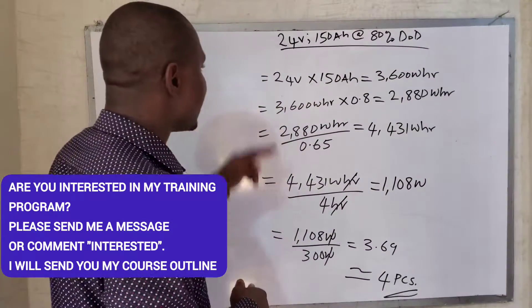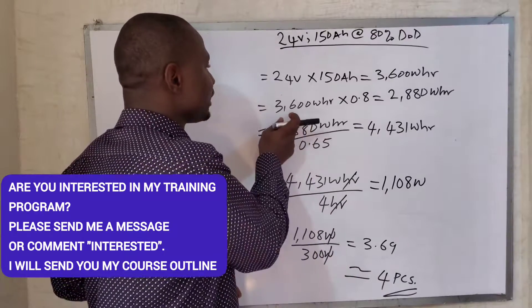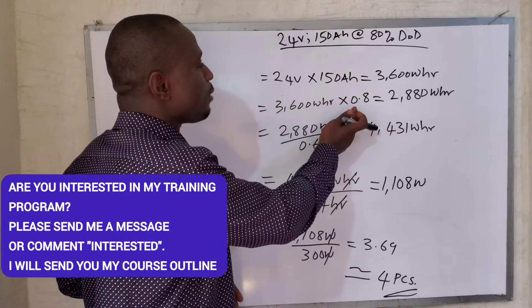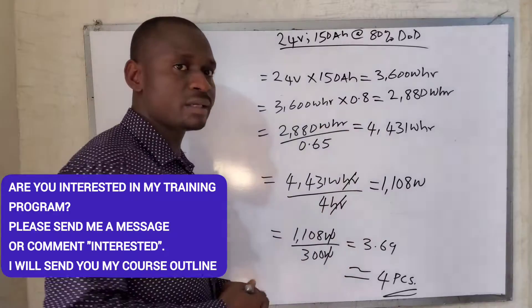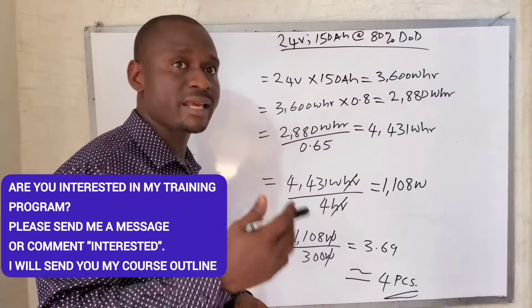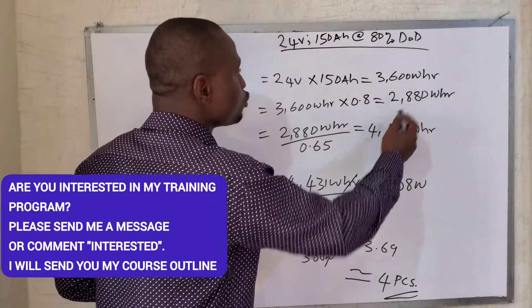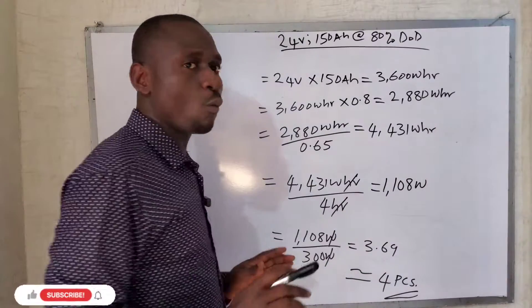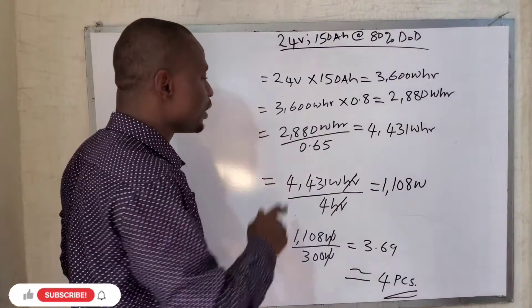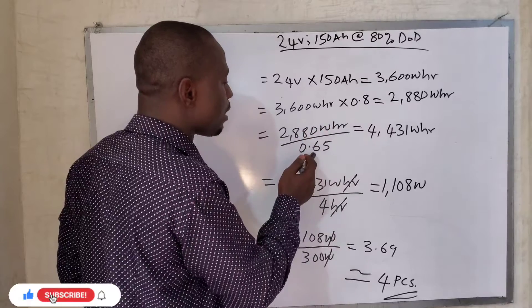Now at 80% DoD, it will be 3,600 watt-hours multiplied by 0.8 (that's 80 divided by 100). This will give you 2,880 watt-hours. Now in the next step, you divide this 2,880 watt-hours by the performance ratio of the solar panels.